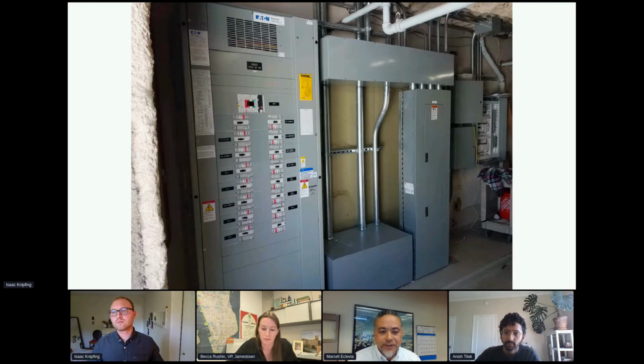Well, we ended up doing a full mechanical upgrade, so we replaced everything on our rooftops. But I think one of the things that's important, especially when you're replacing the majority of your equipment, is making sure that your electrical switchgear or your motor control centers, which power this equipment on the roof, is in order. So you want to make sure that you do a full survey, investigation, and maintenance of this equipment, and make sure everything is good.